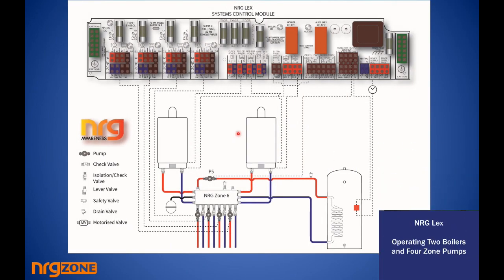So when you look at how that might be applied, I haven't shown the detailed wiring, but let's say for instance you have clocks and stats or whatever here, that zone would operate a given pump. The second zone wiring wise would operate the second pump, third and fourth, and so on. The power supply for a boiler would come from the power supplies coming in this line here on this one, and then the control for the boiler would come on this line and come down and operate that boiler, and separately the second switch will come down and operate that boiler.